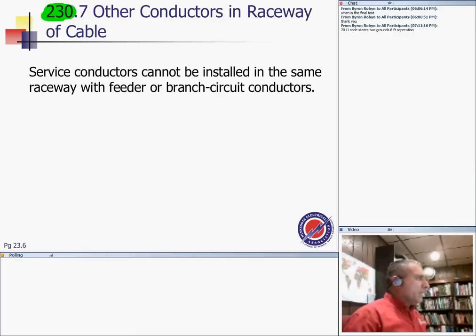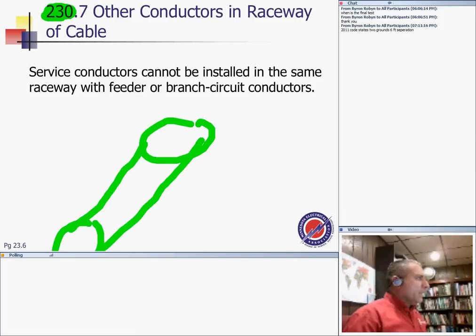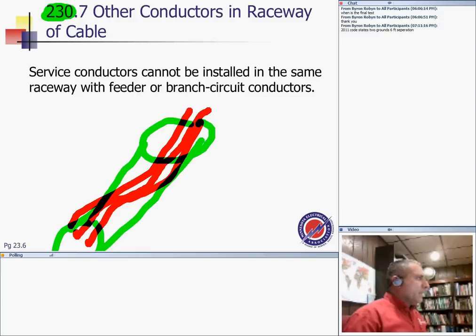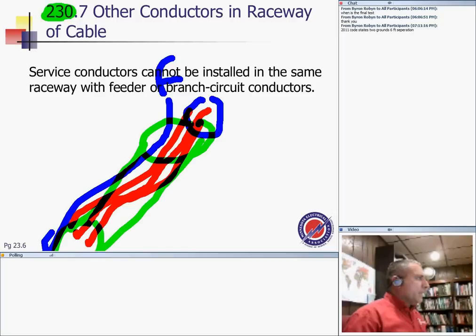Other conductors in the raceway, can I put them in the same raceway? If you have a raceway here, guys, and you're bringing inside your raceway your feeders, 1, 2, and 3 conductors coming in it. I can't bring a feeder with the service. So feeder, and you are my service. You can't do that.